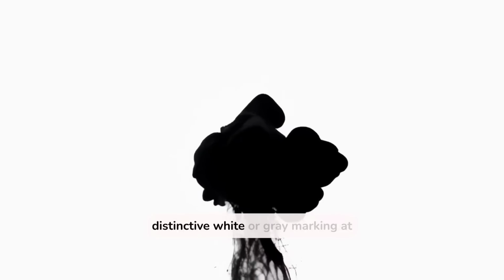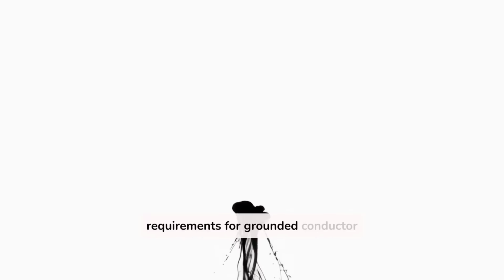6. The grounded conductor of a mineral-insulated metal-sheathed cable, type MI, shall be identified at the time of installation by a distinctive white or gray marking at its terminations. The marking shall encircle the conductor insulation. 7. Fixture wire shall comply with the requirements for grounded conductor identification in accordance with 402.8.